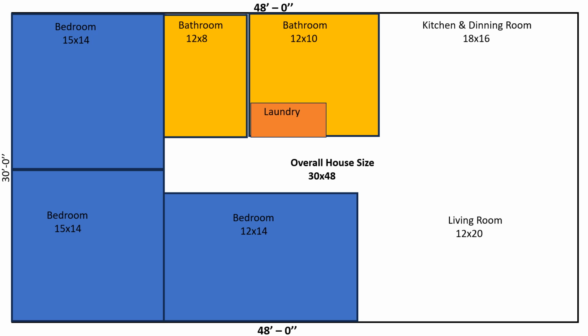Some people go in and divide it by 600, and you wind up with 2.4. So somebody had a real good deal on a 2 ton unit, they put it in, and it's been in there for years. The homeowner says, hey, this thing's been in here forever, we just want something more efficient, or my light bill seems to be higher, whatever the case may be. I'm going to tell you what ICP uses: 30 times 48 equals 1,440 square feet, and they divide it by 500. ICP says 500 square feet per ton, so not 600. And I've heard 100 people say it differently.